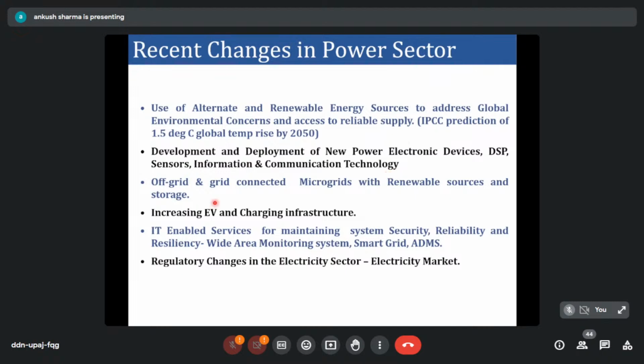Off-grid and grid-connected microgrids with renewable sources are coming up, which include storage as well. A lot of islanded and grid-connected microgrids are being developed. This helps make a small section of load self-sufficient, but it poses more challenges, because the moment you have a fault in the system, the islanding operation of the microgrid needs to be addressed properly.